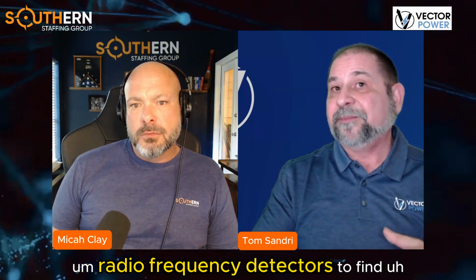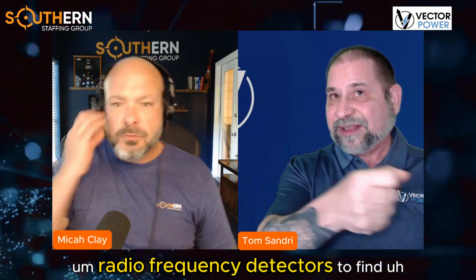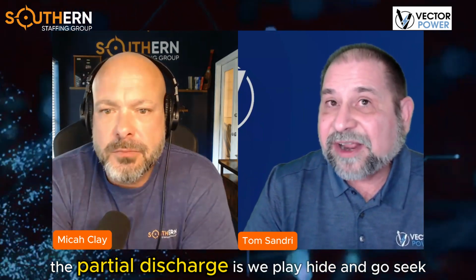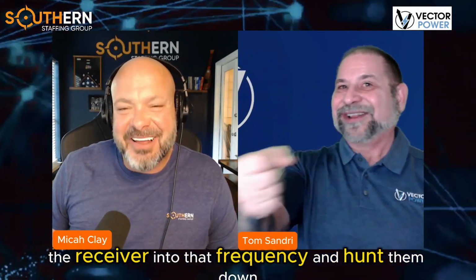Oh, it's interesting. When I get into the world of online partial discharge testing, where we're taking scanning tools into a substation, your SCADA systems operating around 900 megahertz start to become interference. Matter of fact, the way I teach a lot of young technicians how to use the radio frequency detectors to find partial discharge is we play hide and go seek. They'll be on a walkie-talkie broadcasting at a certain frequency band, and I have them hide behind gear, and we basically just tune the receiver into that frequency and hunt them down.